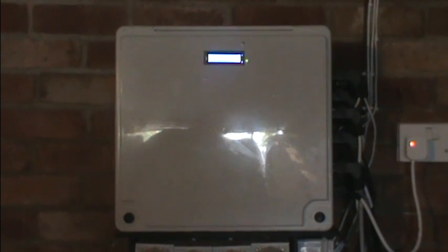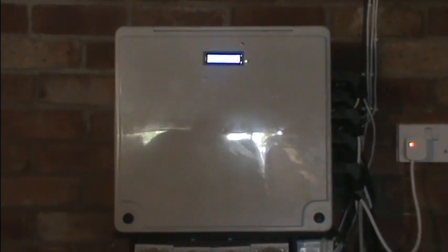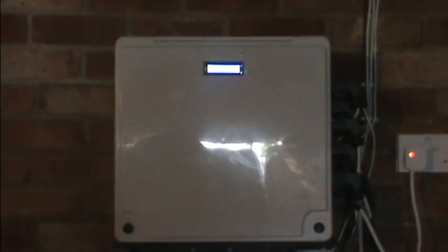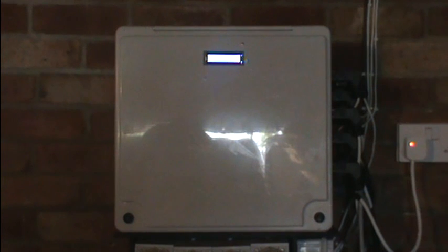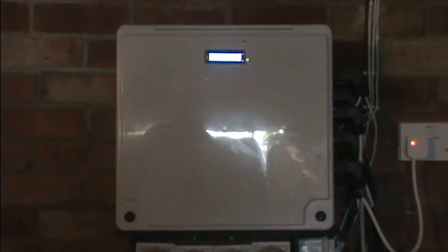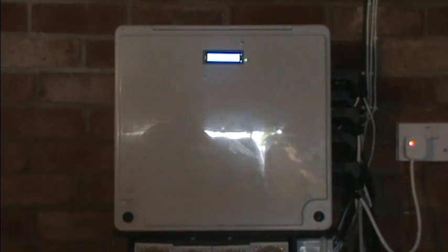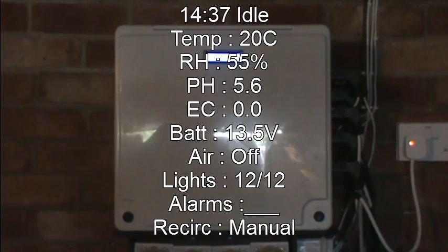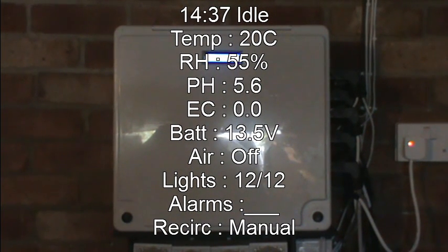Okay, you're going to request a status report to see exactly what state the system's currently at. So send in the command status. Okay, current time and status, which is currently idle, temperature within the room, humidity within the room, current pH, this isn't currently right because the probe isn't submerged and it's still slightly wet, and the EC value.